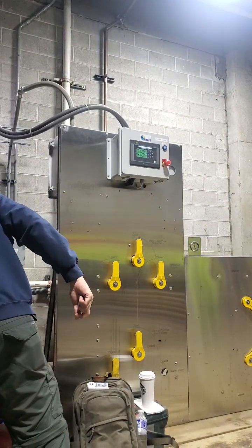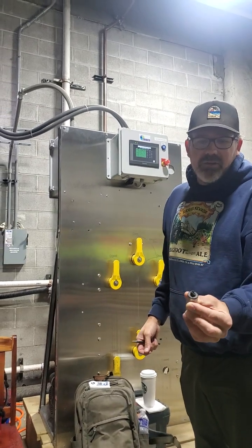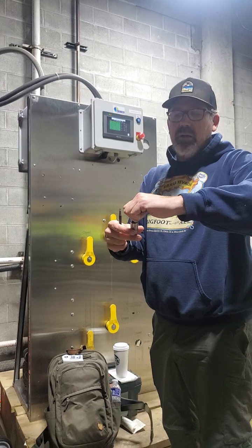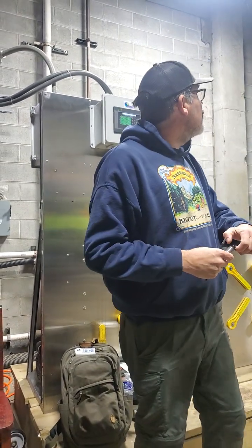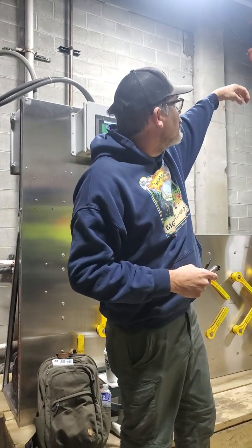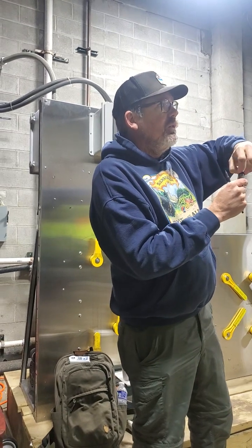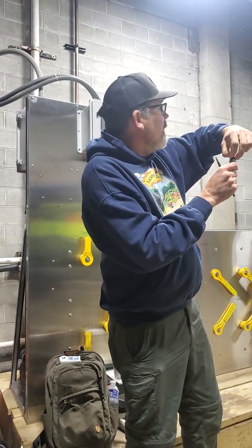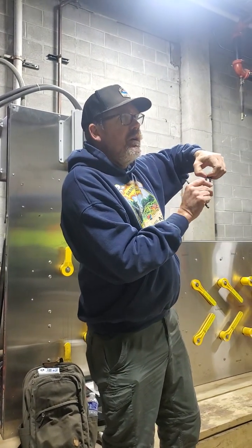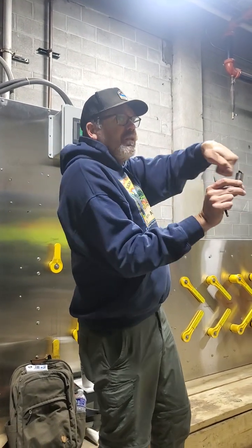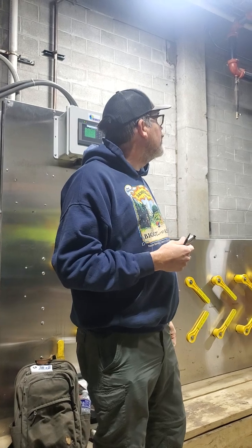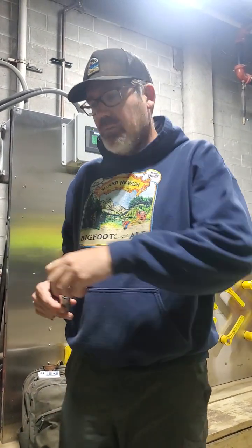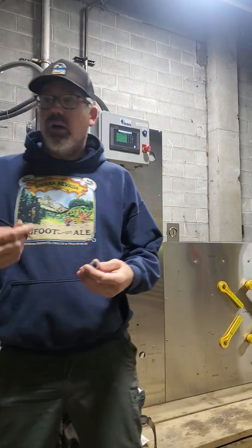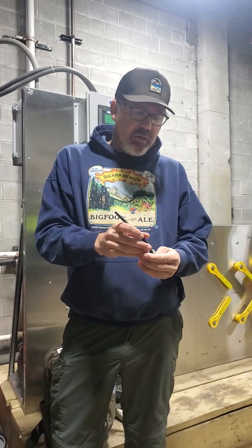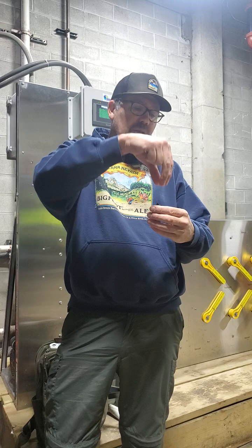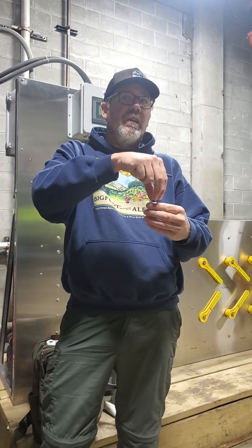So this is what happened to that one up there. What I'm guessing is somebody went up there and, instead of trying to unscrew it properly, grabbed the elbow and just twisted it, shredded the thing and broke it. I don't know if you can see it up there, but there's a little silver piece that sits on top of the connector. That's where you unscrew it. Don't grab the connector on top and try to unscrew it. You have to grab that little silver nut and unscrew it from there. Then you just pull it straight up. Tighten it back hand tight. Like I said, don't caveman it. There's a little keyway on there that you have to line up with the connector, and it won't screw down unless you have that keyway lined up.